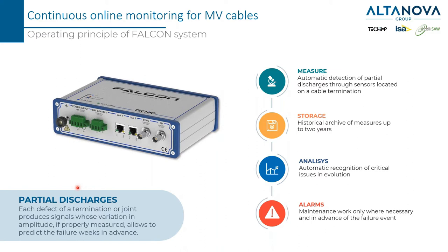Falcon is a device that measures the partial discharge activities of the cable itself. The medium voltage cable is made of several pieces connected together — this connection is called a joint — and the joint is the most critical part of the medium voltage cable, so the highest probability of a failure is inside one of these joints. Whenever there is a defect, it produces a little spark, which is in the end a partial discharge — an electrical signal in the range of very high frequency, in the megahertz range, that travels along the cable and reaches the sensor.